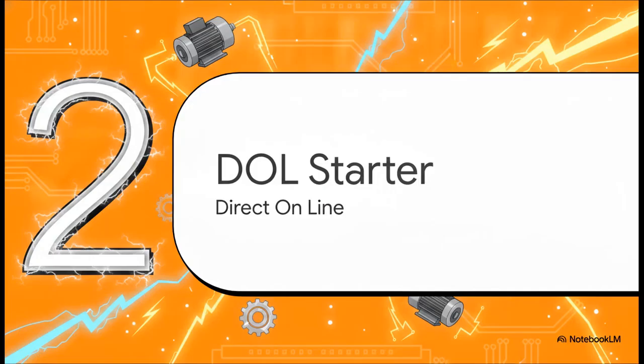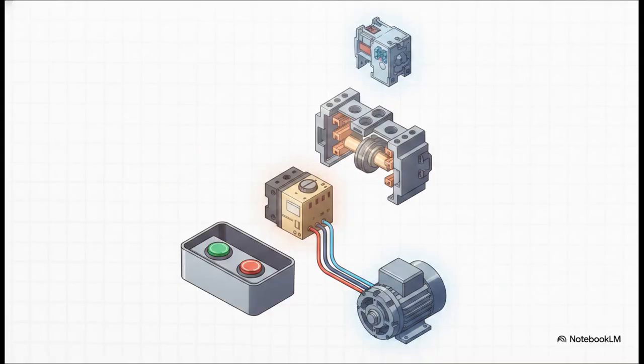Moving on to Section 2, Direct Online or DOL. Let's look at the most basic starter out there, the DOL starter. It's got a wonderfully simple setup. You've got an MCB or MCCB to manage the main supply, a contactor to actually connect and disconnect the motor, and an overload relay to keep it safe from, well, overloads. Plus, of course, those classic green and red start and stop push buttons. It's totally perfect for smaller motors, but here's the catch. It doesn't reduce the starting current at all. It just connects the motor straight to the supply.